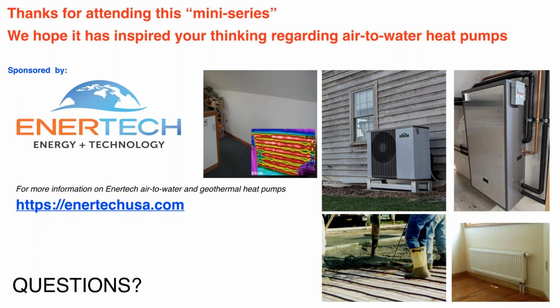Anytime we're cooling with chilled water, it is going to be less efficient than a DX system, but we also get the advantage of domestic hot water. So if you look at it on an annual basis, I haven't done any calculations in Florida, but in Texas, with the exception of this week probably, if you look at domestic hot water and you look at heating and cooling, the cooling efficiencies are less with a hydronic product like this than they would be with a DX. But if you have enough hot water load, it's easily offset. So we have to really look at the total system rather than just specific efficiencies. So it's going to depend also on how much hot water load you have versus cooling load, that kind of thing. But in general, the DX efficiency is going to be a little bit better. It just doesn't have the capability to do domestic hot water.